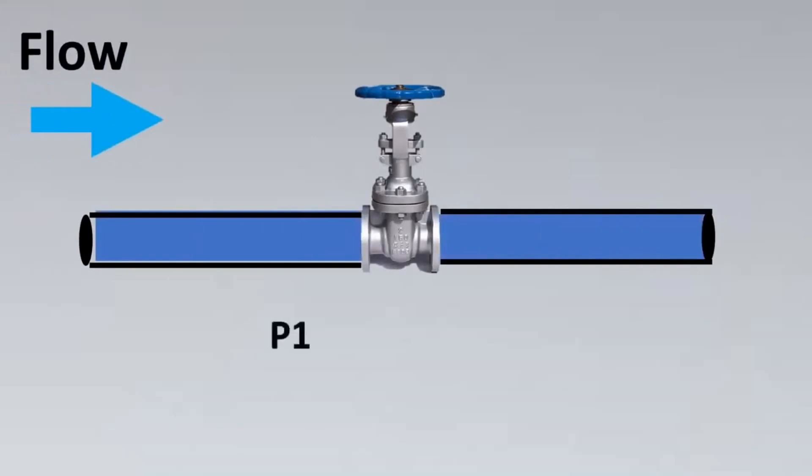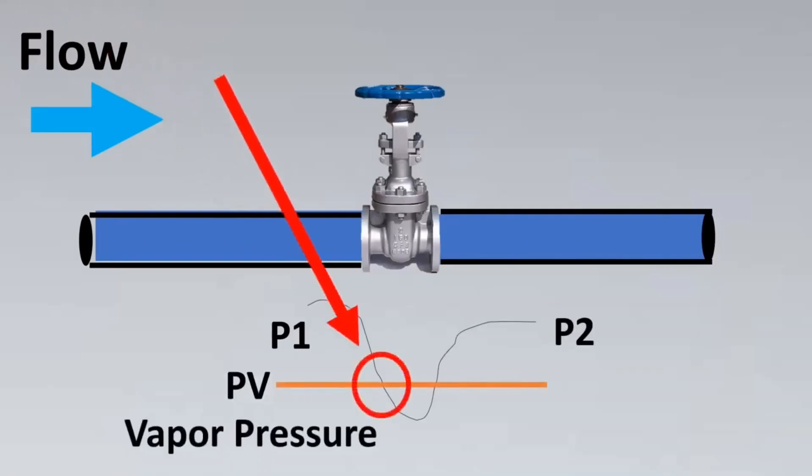Imagine this is your valve put in a line. With the flow there's some restriction, so you have a DP or differential pressure created. The upstream pressure is P1 and the downstream pressure is P2. This is your vapor pressure curve. When the fluid is at this particular region, it's going to change from liquid state to vapor state.